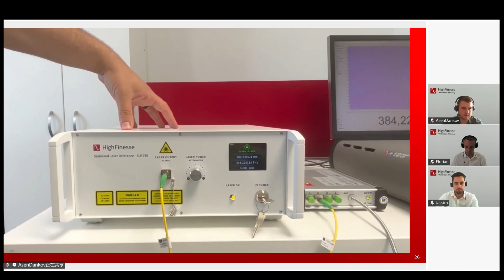Here we have the SLR 780 laser. This is the calibration source that can be used with the wavelength meter. It uses a rubidium cell and it's locked to a well-known atomic transition. As a rule of thumb, the calibration source that you use with the wavelength meter should be at least 5 times more accurate than the wavelength meter specified measurement accuracy.